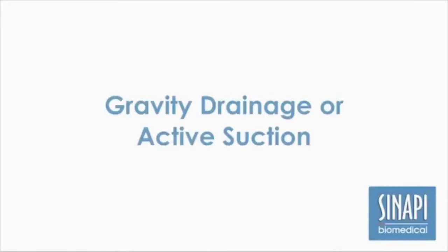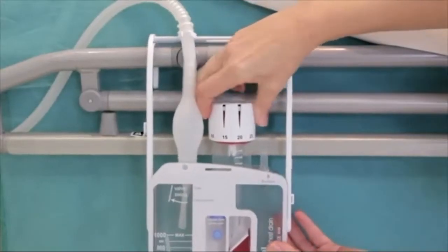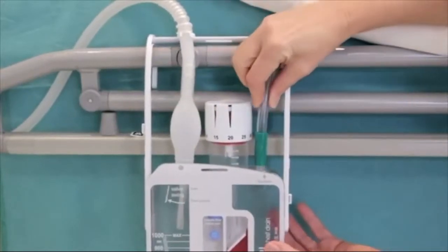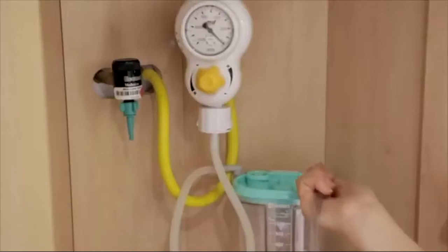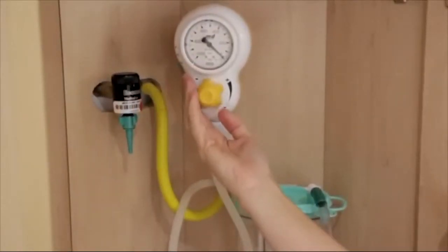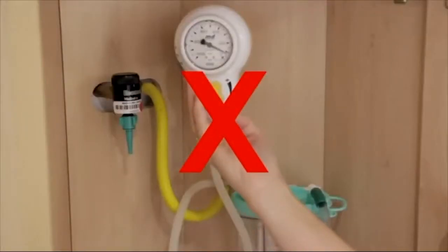Use a Sinapi chest drain for gravity drainage or active suction. To initiate active suction, set the white suction knob to the required value. Connect the tubing from the vacuum source to the suction port. Slowly increase the wall suction from zero until the red bellows reaches the set value. Do not increase wall suction further, as this will increase noise levels.